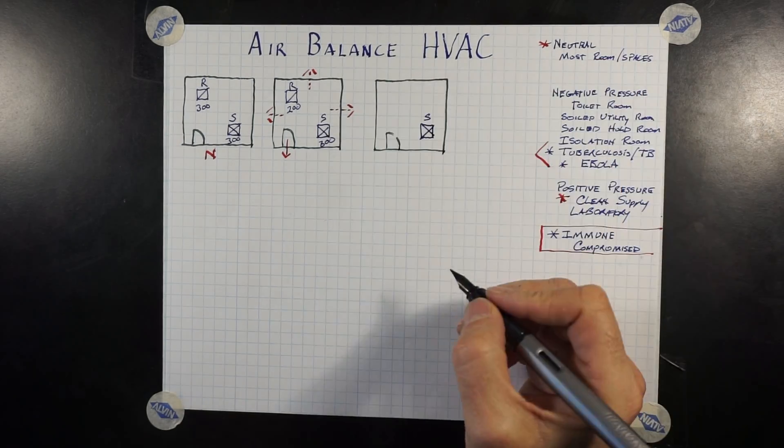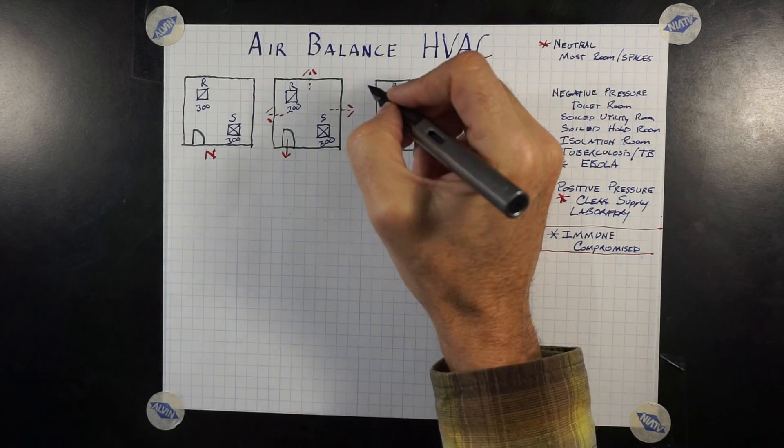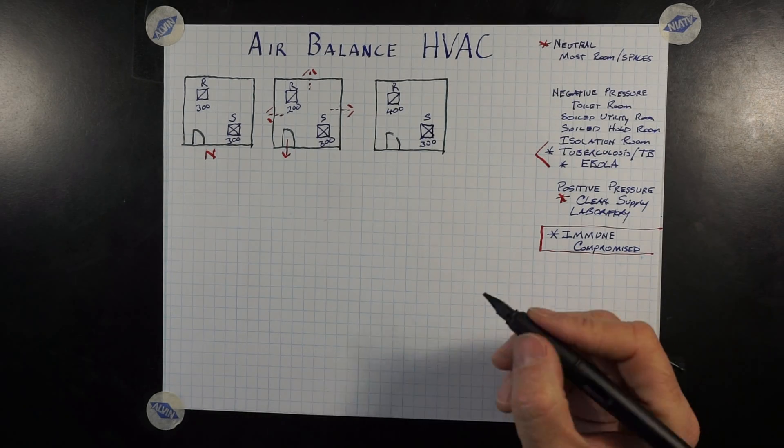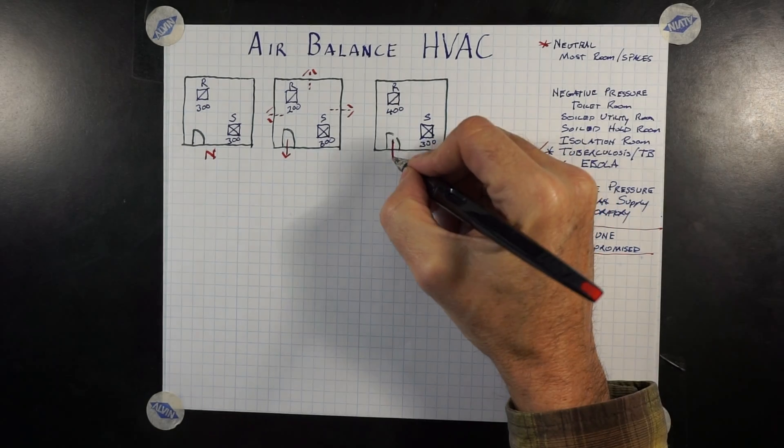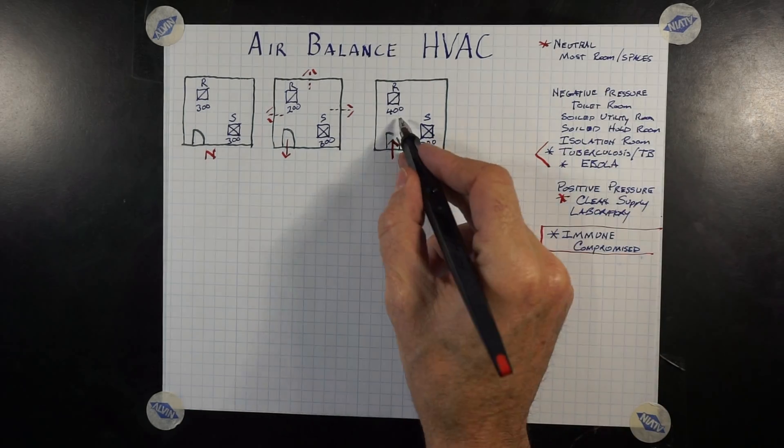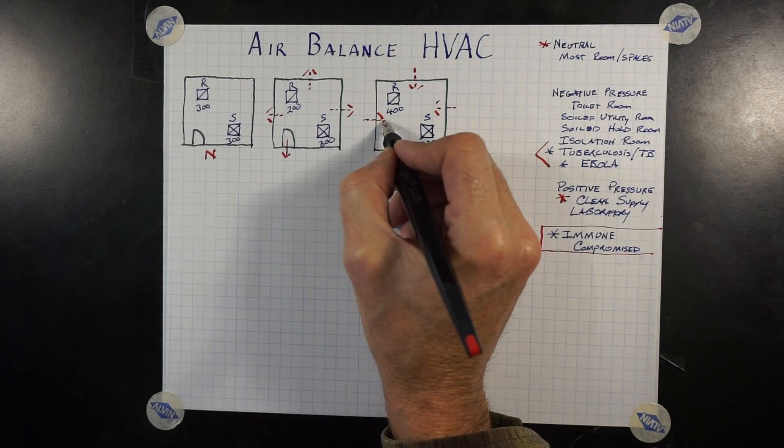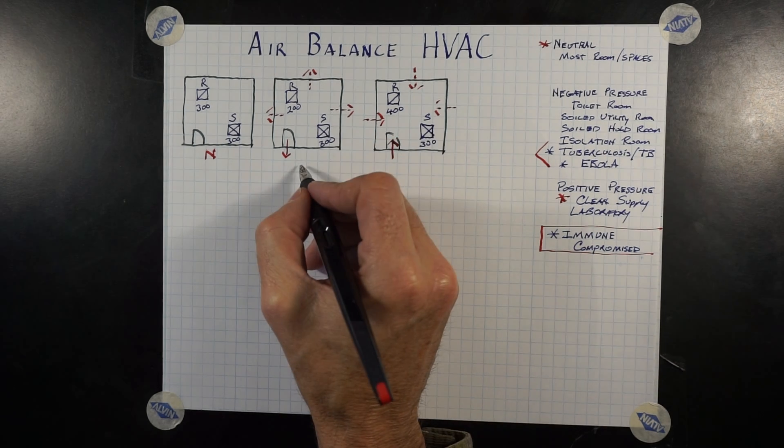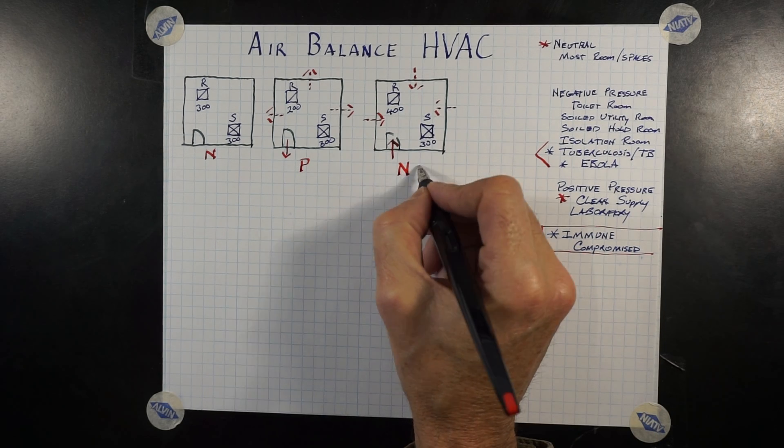With this room, we have a supply of 300 cubic feet of air coming into the room. We have a return of 400 cubic feet of air. That means there's more air being sucked out of the room than being supplied. So when the door is open, more air will flow through the door. When the door is shut, air will come in through the walls to make up for that additional cubic feet of air needed for the return side. So this room here is positive, and this room here is negative.